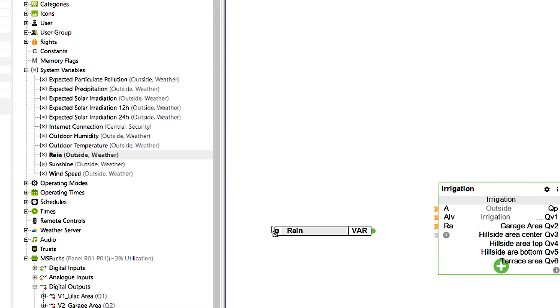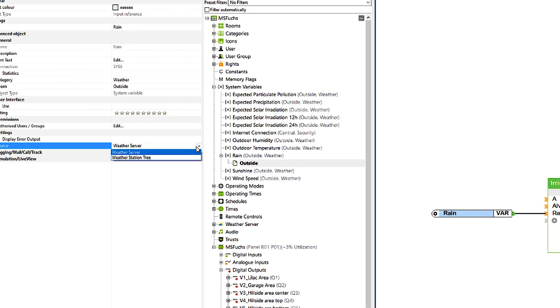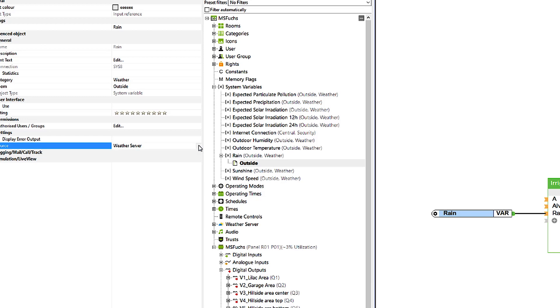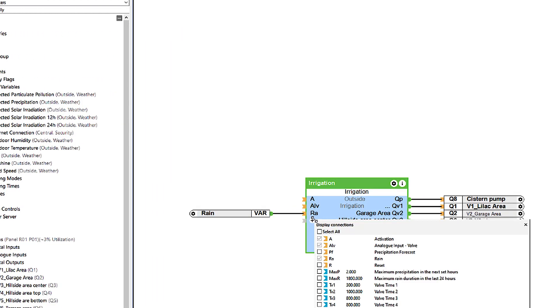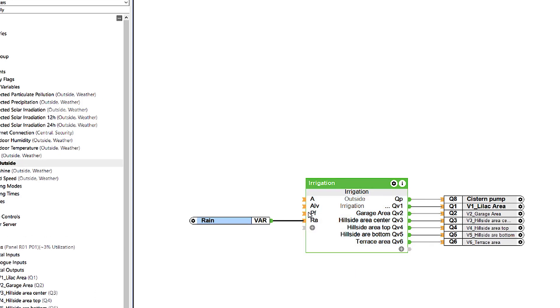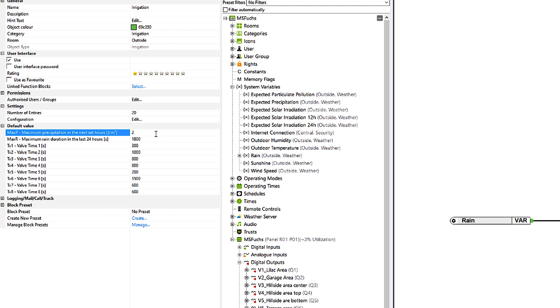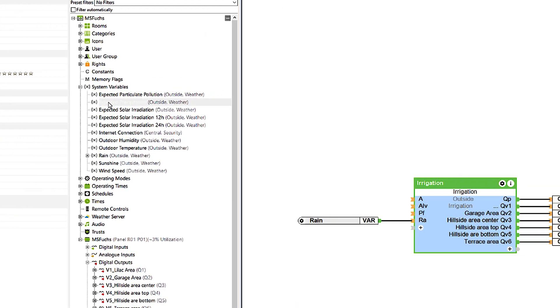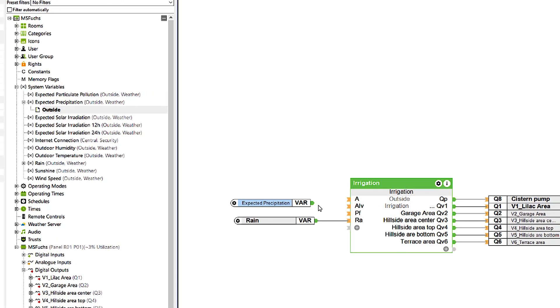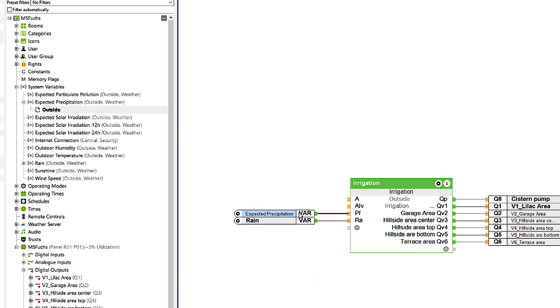I use the system variable rain for this purpose. You can decide individually in the properties whether the values should come from the weather station or the weather service. In order to include the expected precipitation in the irrigation system, the block has the input Pf and the associated parameter maxP. The system variable expected precipitation indicates the sum of the expected precipitation in liters per square meter, and the maximum permissible precipitation can be freely defined via the maxP parameter.